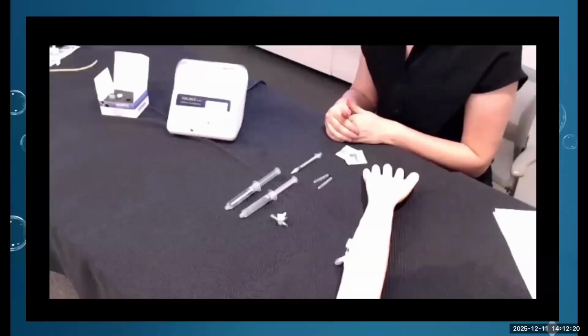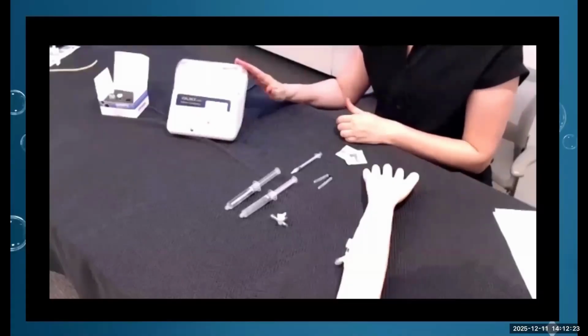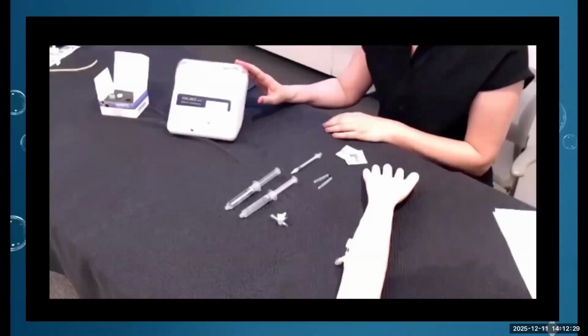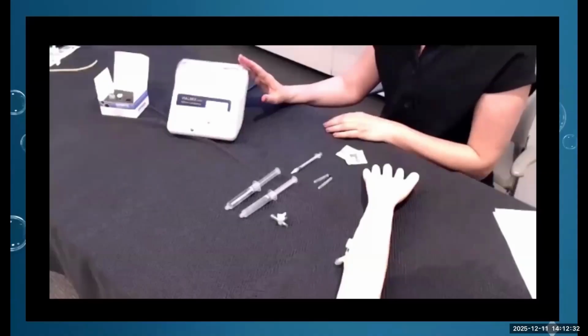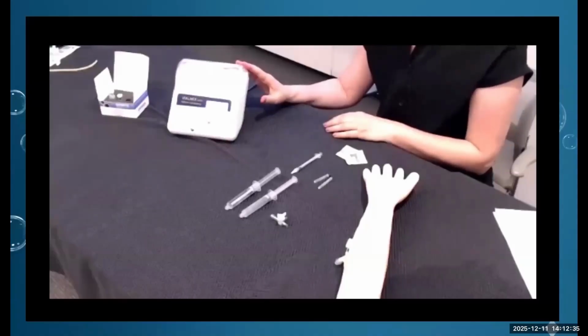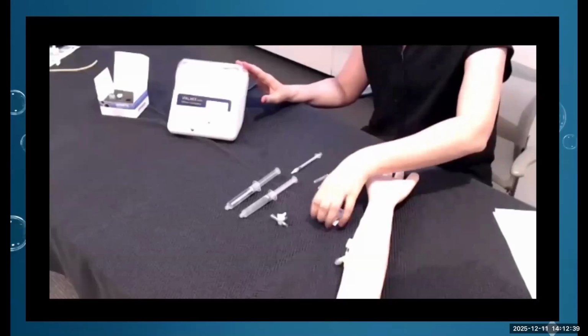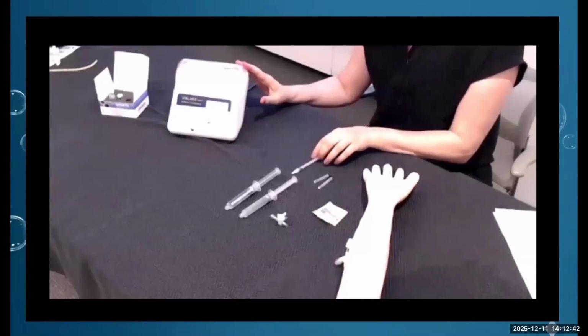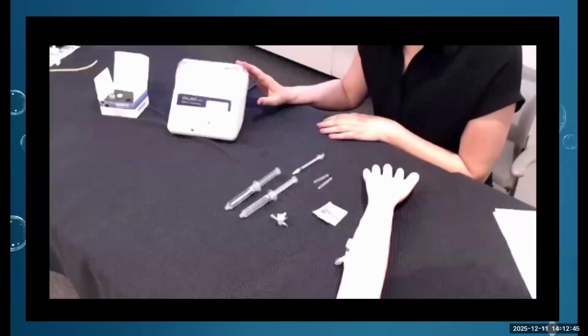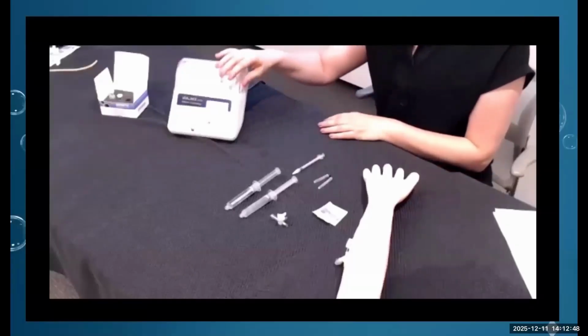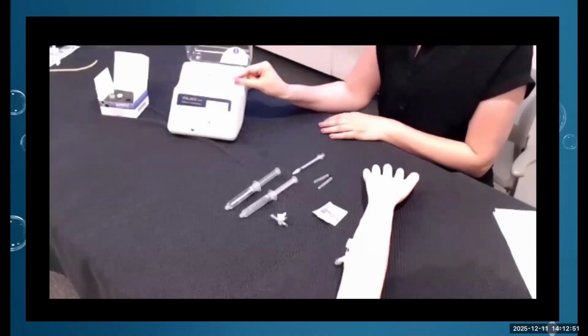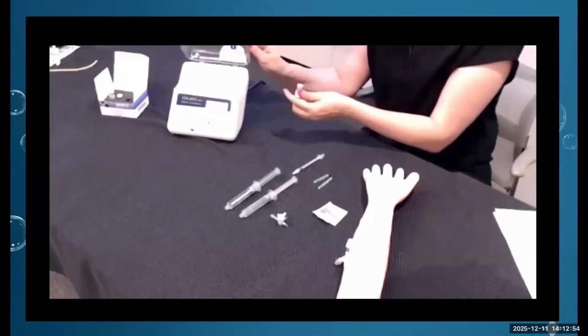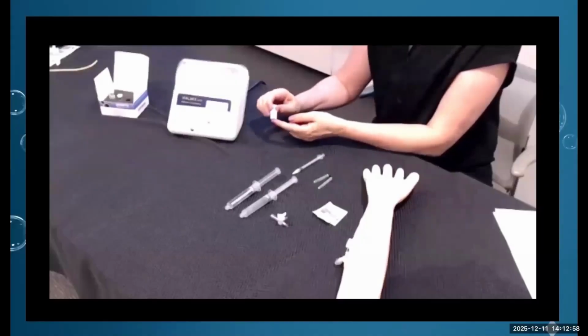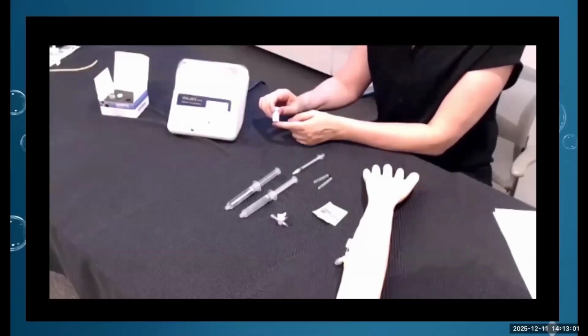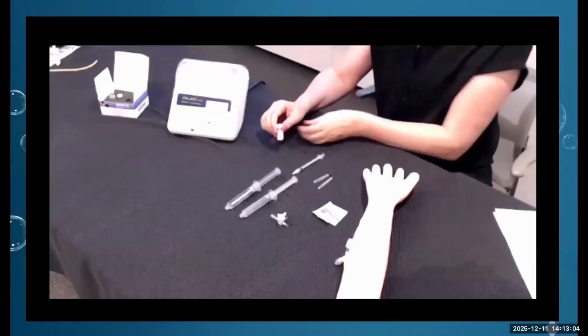The Vial Mix is a mechanical agitator. It has an automatic 45-second activation cycle. You want to ensure that once the Vial Mix is started, you do not interrupt the cycle or lift the cover. Mechanical agitation allows for a consistent size and distribution of microbubbles, stabilizing them in solution. From extensive experience, we find the Vial Mix easy to use, and it lasts for many years through multiple series of bubble activations. When the activation cycle is complete, you lift the cover, press down on the tab, push it sideways, and remove the Definity from the Vial Mix. You'll notice that the Definity is now a homogeneous, milky, opaque white and fully activated.